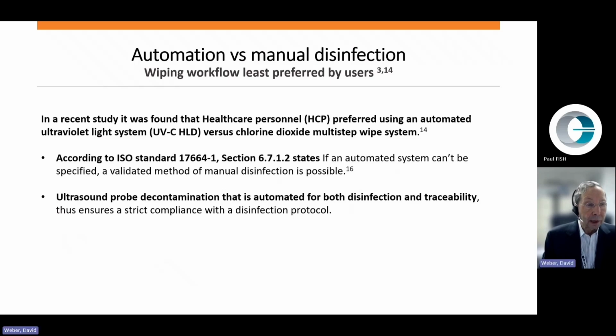According to ISO standard 17664-1, section 6.7.1.2 states, if an automated system can't be specified, a validated method of manual disinfection is possible. Ultrasound probe decontamination that is automated for both disinfection and traceability thus ensures strict compliance with the disinfection protocol.